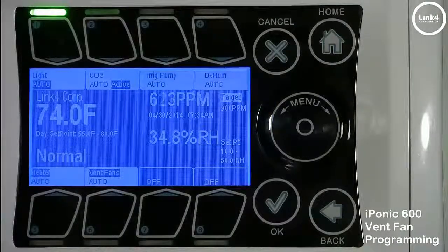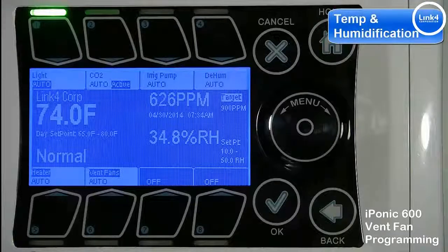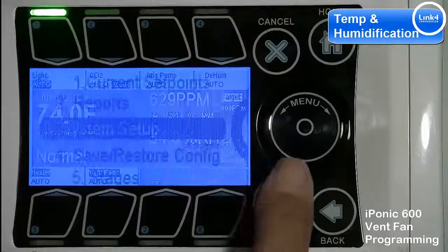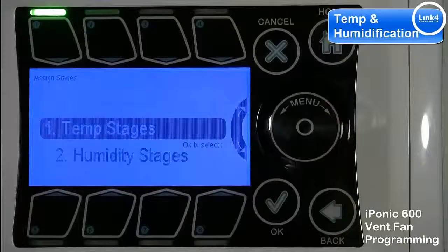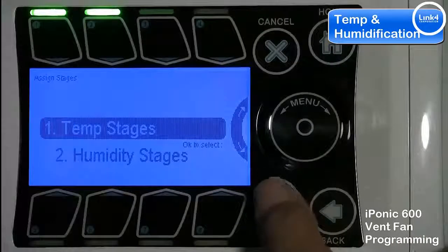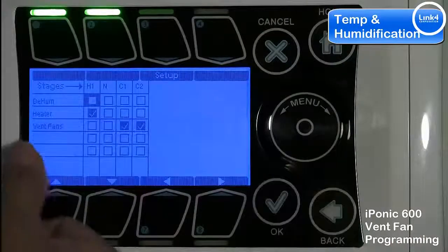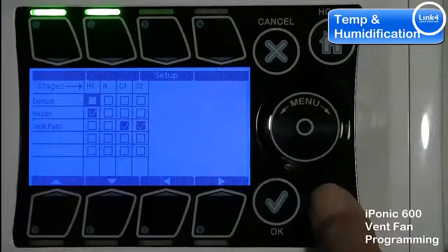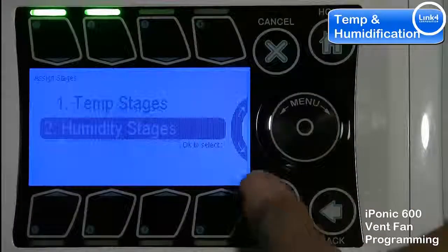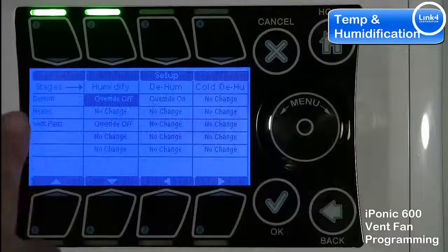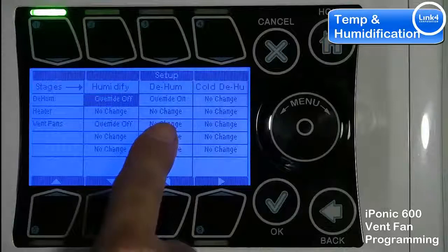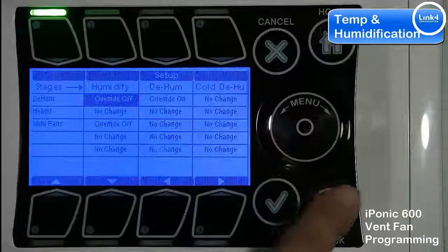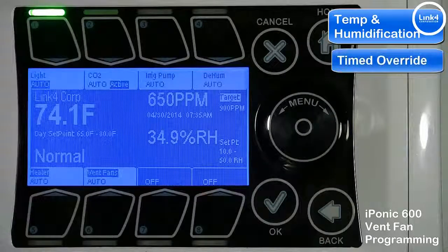The vent fan can come on during cooling or humidification — it can come on separately or simultaneously by going into stages. If you hit stages number five, you will see temp stages and humidity stages. You can assign your vent fan to come on during your cooling stages, or during humidification by changing the setting from 'no change' to 'override on'.